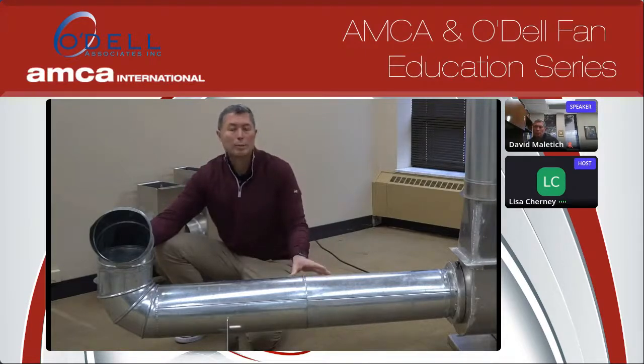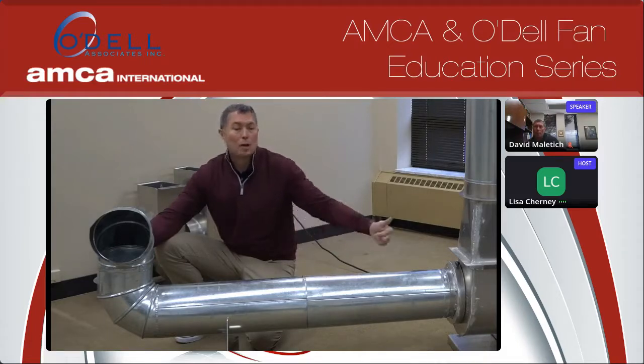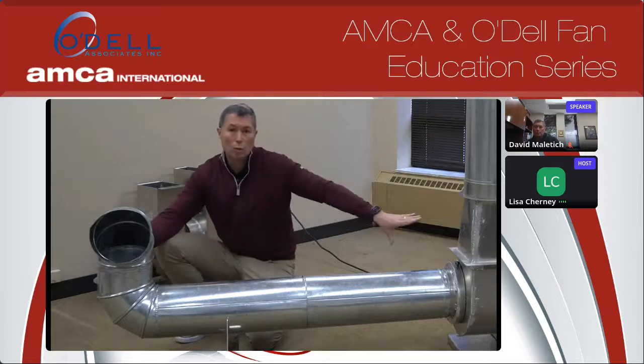Now, the only way to eliminate that is to put perhaps a T or a cross section in the duct, known as a vortex breaker, to help break that vortex and prevent that pre-spin from continuing from here all the way into the inlet of the fan.